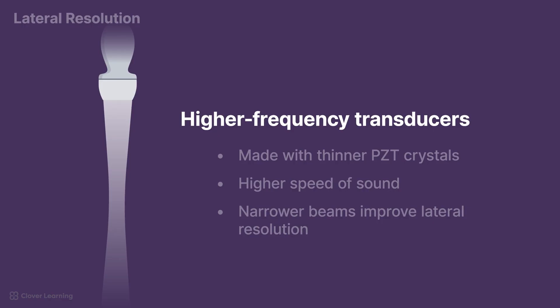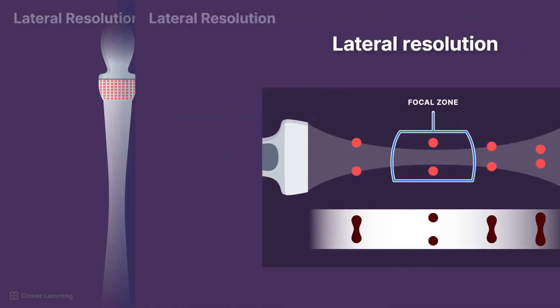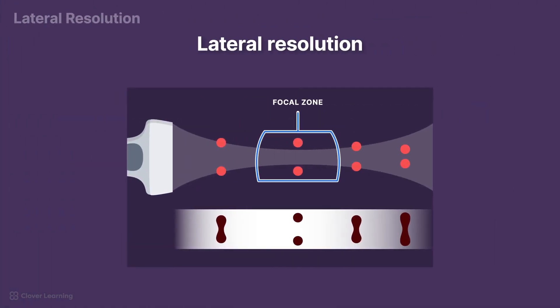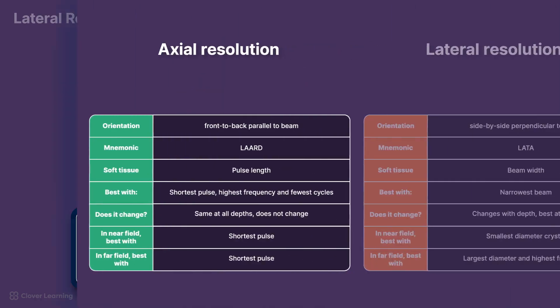Higher frequency transducers are made with thinner PZT crystals that have a higher speed of sound. This allows them to produce narrower beams, thus improving lateral resolution. Unlike axial resolution, which remains constant at all depths, lateral resolution varies with depth. It is best at the focus of the beam, which makes beam focusing techniques essential for optimizing image clarity in specific regions of interest.